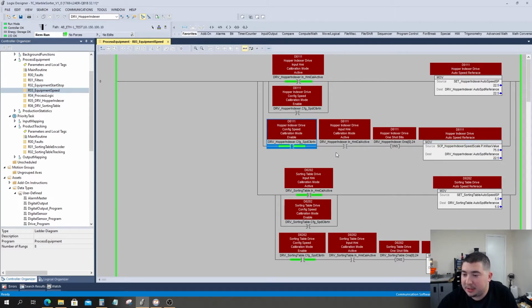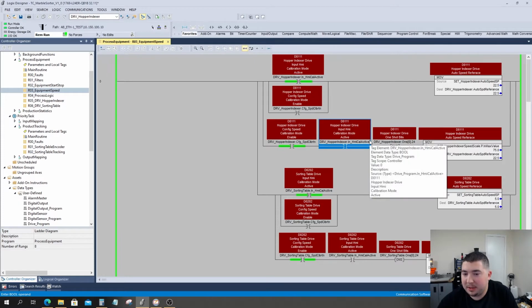I have a few configuration bits to ensure that our calibration mode is available and active. So the first bit here is a config bit. This allows the user to do a speed calibration via the HMI. This means that you are allowed to do the speed calibration mode. If this bit's not active, then no speed calibration will be done. The next bit is to indicate whether we're actually in a calibration active mode or not. If we're not, then the speed value is just going to be the actual auto speed set point. If we are in calibration mode, we'll send our new value over to our auto speed buffer.